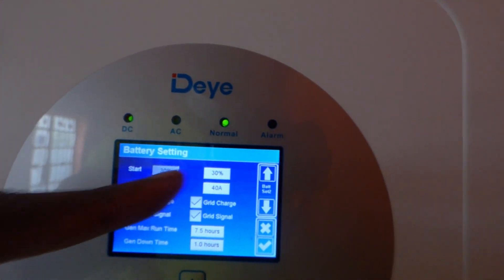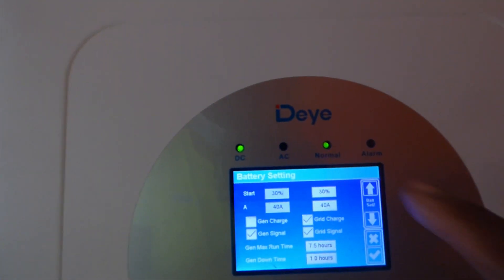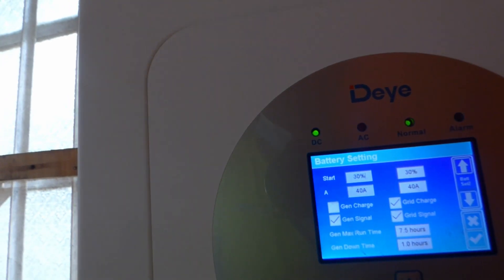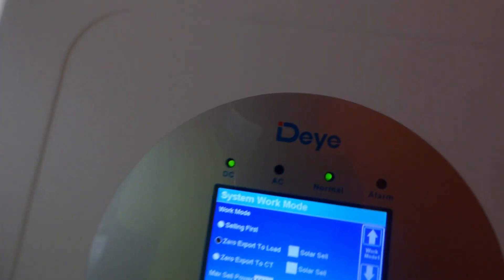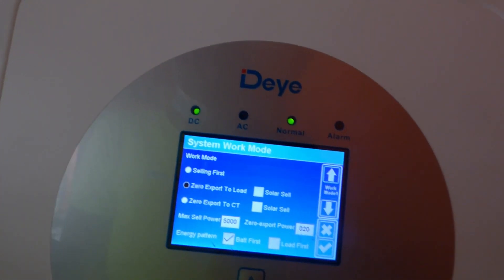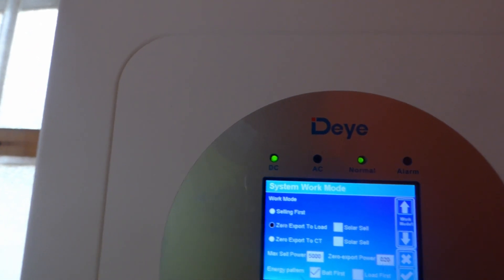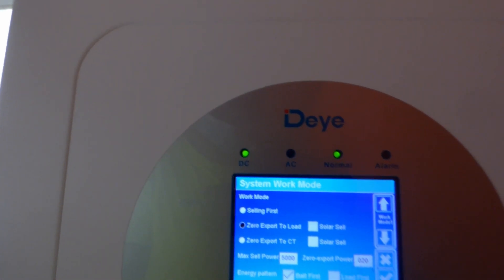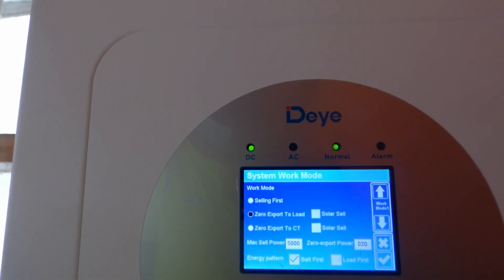You can change these numbers. I'll leave it at 30%. Escape again, and now come back to the system work mode. Set up — you're not selling. In Nigeria, we're not able to sell, so do not sell. And then zero export to load. Now, I can set mine to load first, but because I'm purely off-grid, I will not set it to load first. But for those of you who have the grid, set it to load first — the system will power your load first before it charges the battery.